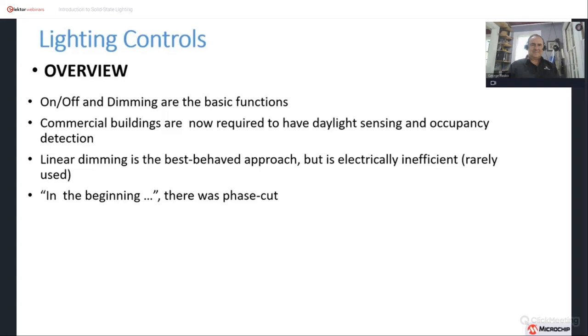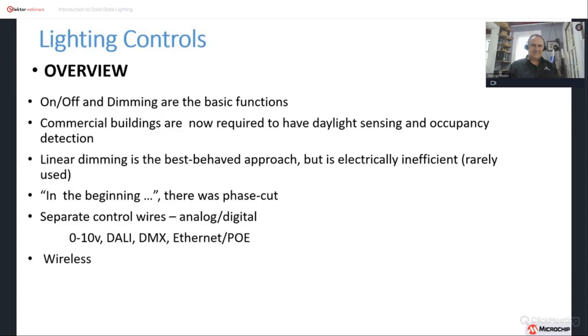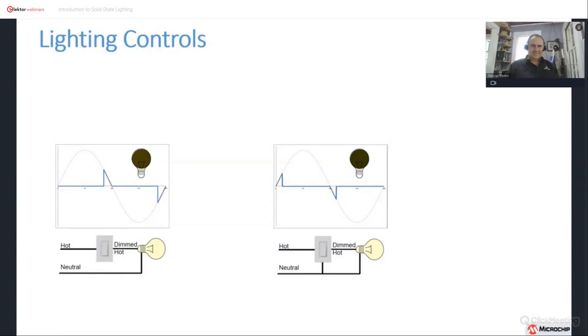The way dimming is done varies. The simplest approach with best behavior is linear dimming, but it's hugely inefficient. The next step is phase cut dimming — this is the reason the Lutron company exists. Dimming and on/off control can be done with analog or digital connections. Some names and processes for this are 0-10 volt, DALI, DMX, Ethernet, and Power over Ethernet. More modern wireless approaches include Bluetooth, Wi-Fi, Zigbee, and LoRa.